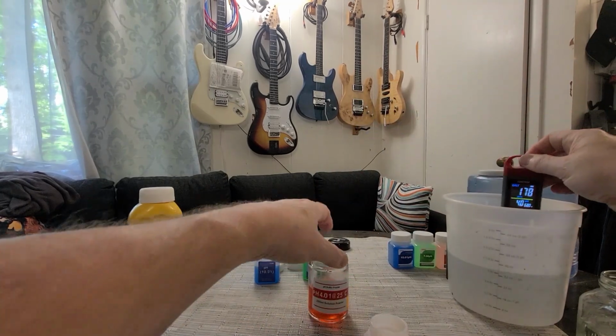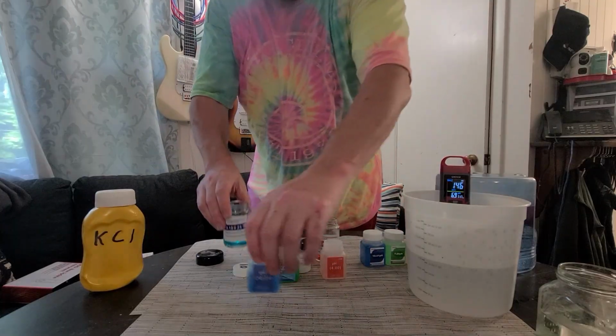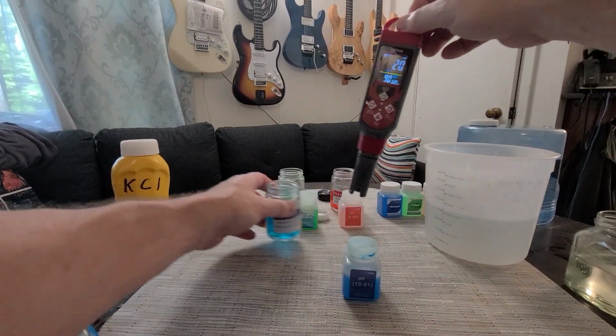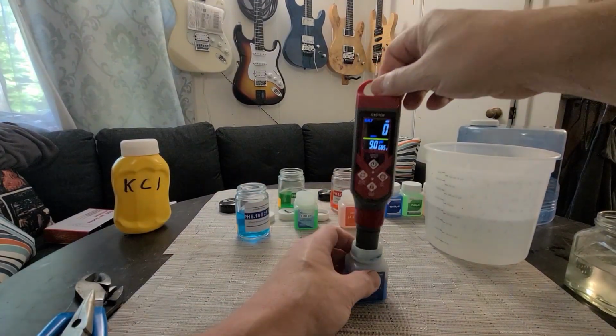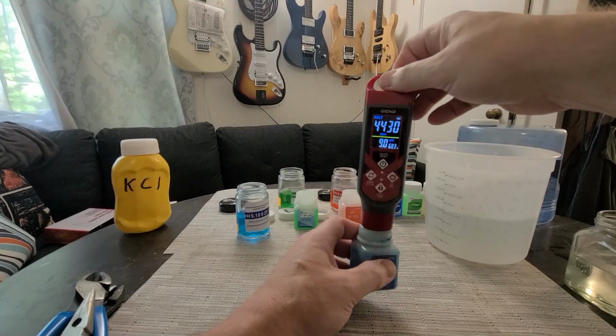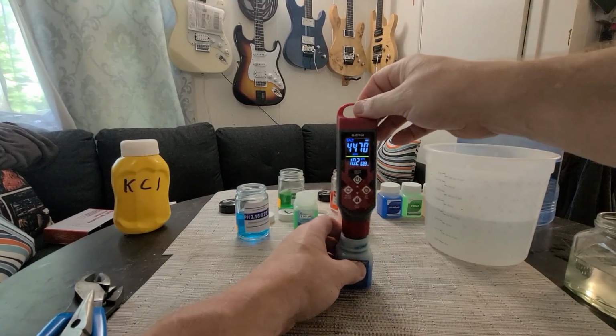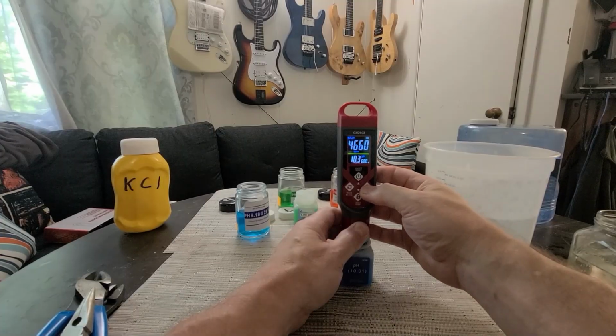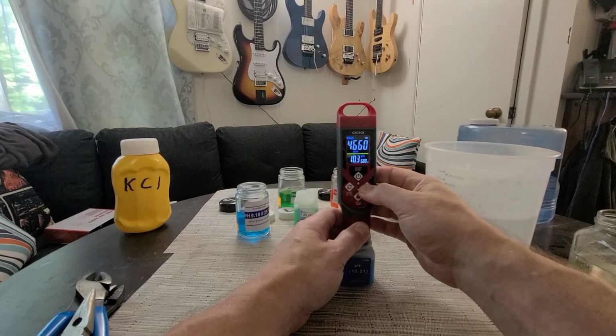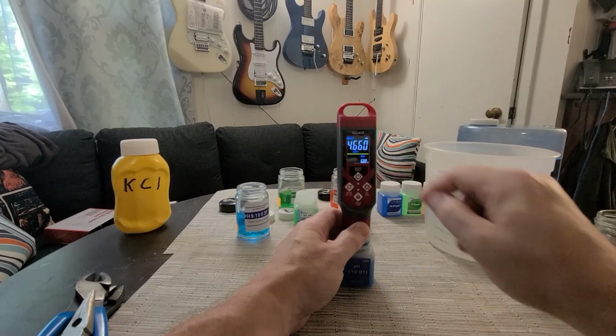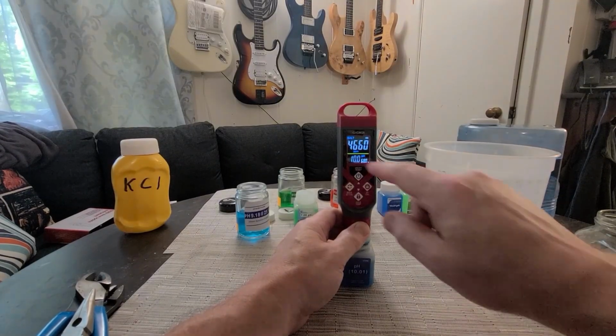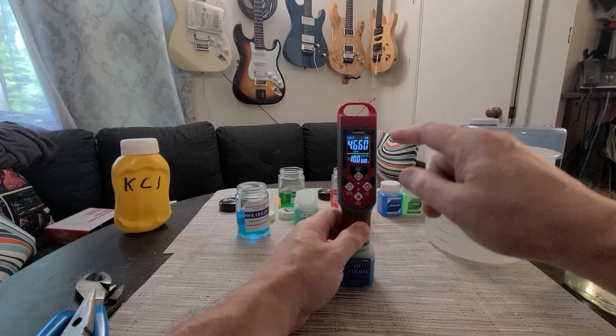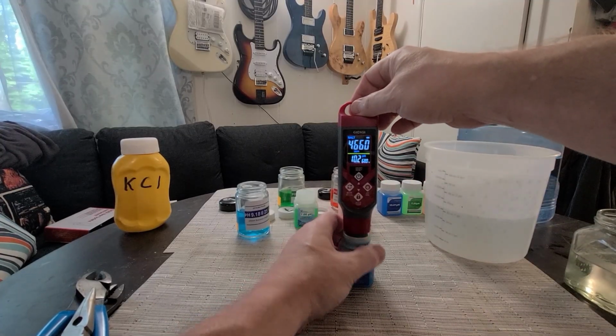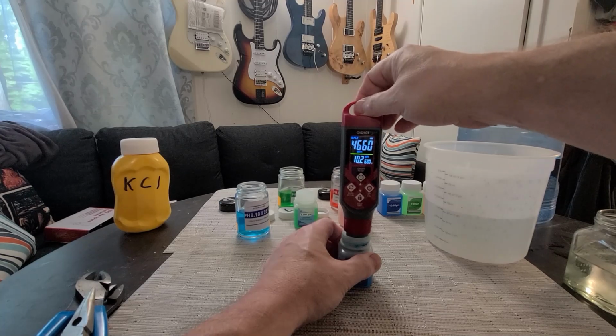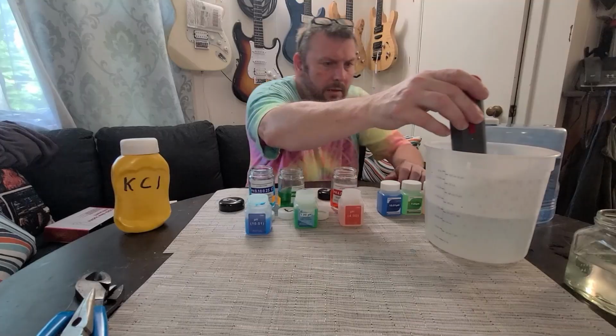So we'll put it back over here. We're going to do the 10. Alright, so it's got the 10 seconds in the pre. Now I'm going to go in the actual testing solution. Shake it around. Try to get the air bubbles out. 5 seconds here. 1, 2, 3, 4, 5. Let go. It's flashing. It thinks it's the 10.0 solution, and then it gave me an OK. So according to them, this thing is actually calibrated now.